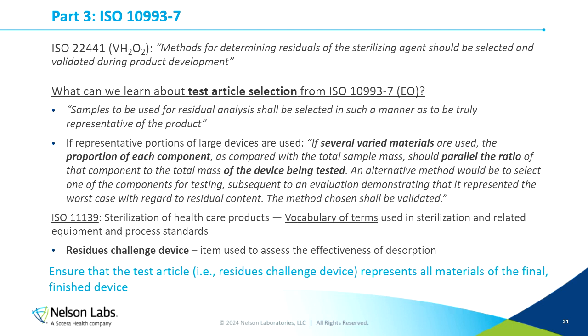There's yet one more standard that I want to bring in briefly, and that's ISO 11139. This standard is essentially just a list of 300 and something terms used for the sterilization process. And the definition that I pulled out is the residues challenge device. A residues challenge device is an item used to assess the effectiveness of desorption. So I just liked including this term because it brings you into the mindset of not being a process challenge device for the efficacy of sterilization, but rather a device that poses the most challenge to residues analysis.